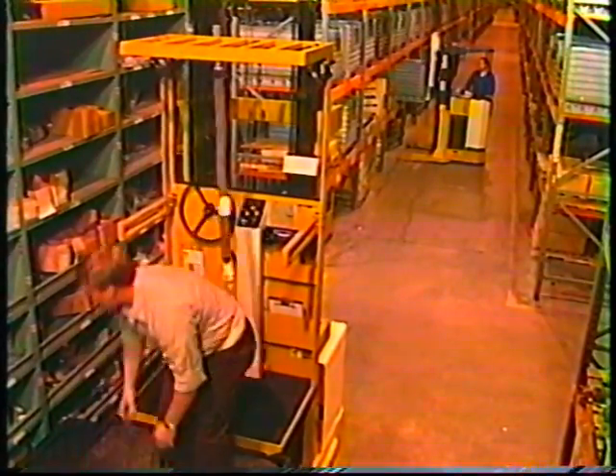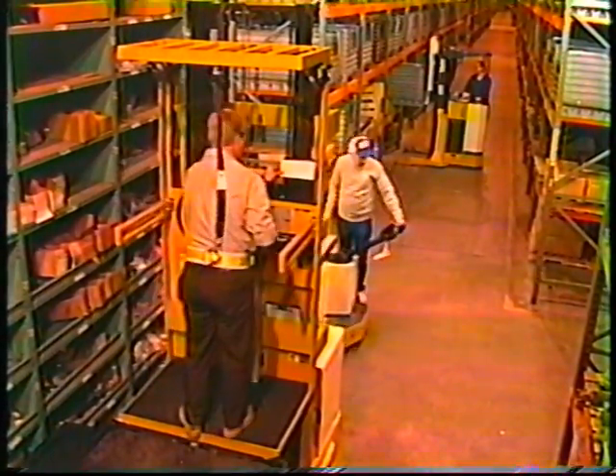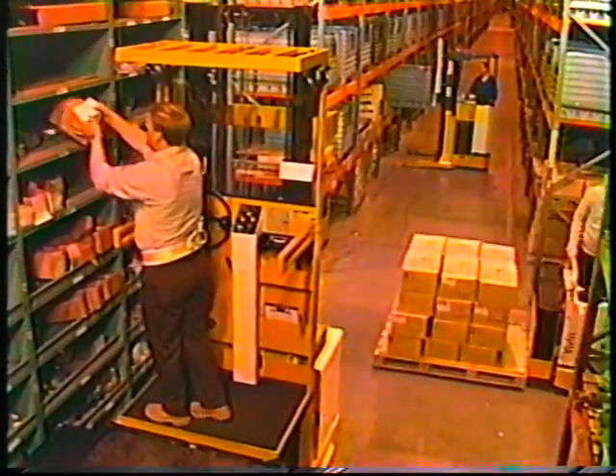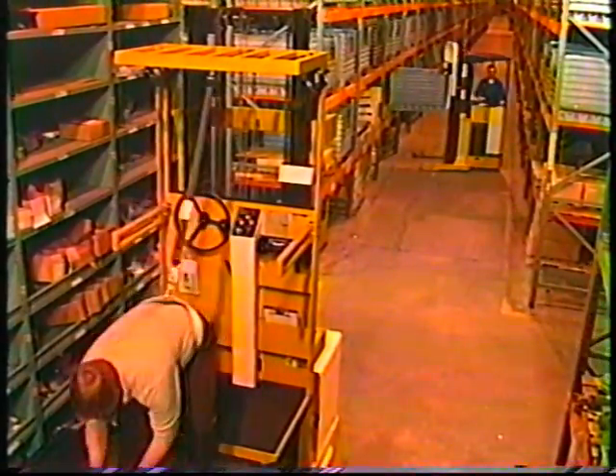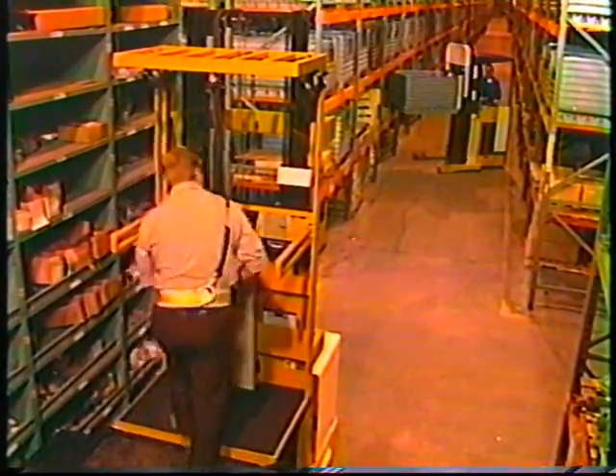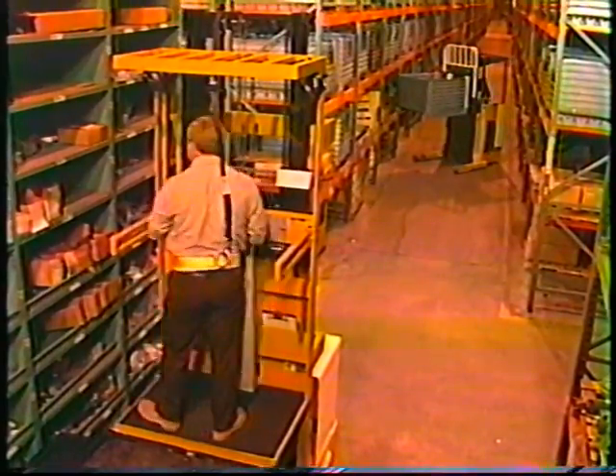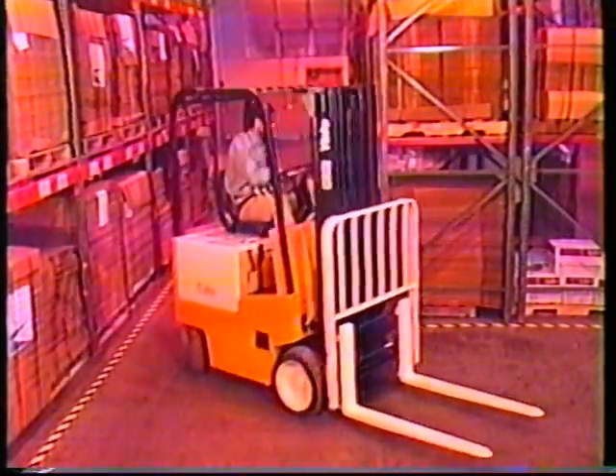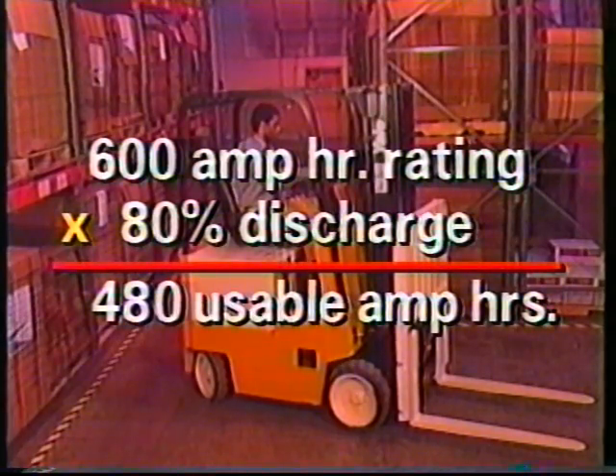Batteries are usually rated for a 6-hour discharge cycle. So a lift truck performing common operations should be able to operate for about 6 hours before we need to recharge its battery. For example, a 600 amp hour battery can deliver 100 amps for 6 hours. However, to ensure maximum battery life, the recommended usable capacity is generally 80% of the rated capacity.